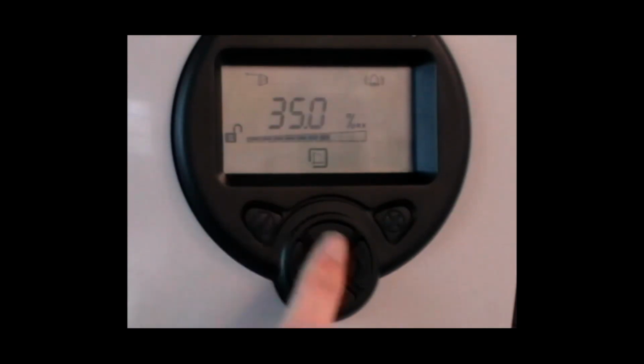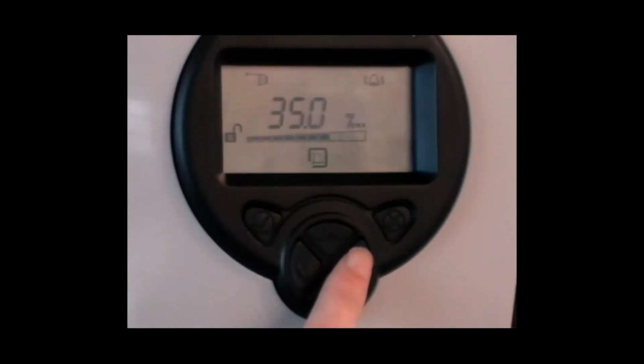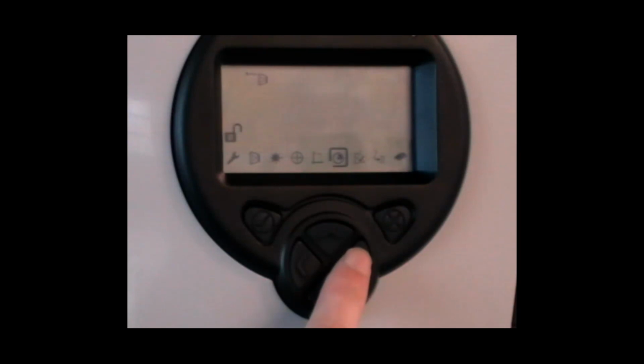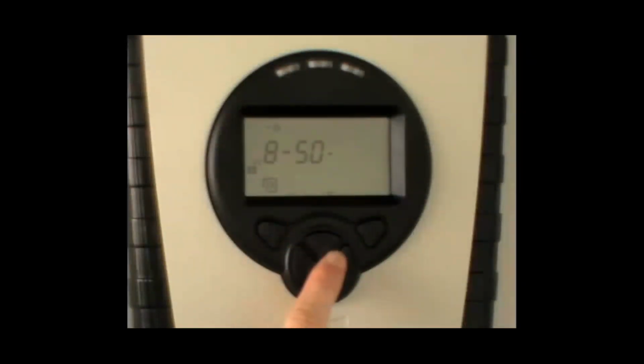There are other settings that can be made. For example, the fire threshold can be set for each detector. The delay to fire can be set for each detector. The delay to fault can be set for each detector. The mode for the system can be set to latching or non-latching. Refer to user guide for further instructions.